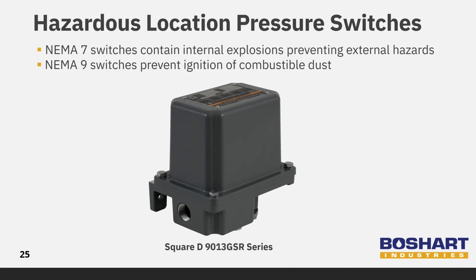Square D's 9013 GSR series is rated to both NEMA 7 and 9. NEMA 7 enclosures are designed to contain an internal explosion without causing an external hazard. NEMA 9 enclosures are designed to prevent the ignition of combustible dust. These enclosures are intended for indoor use in hazardous locations.